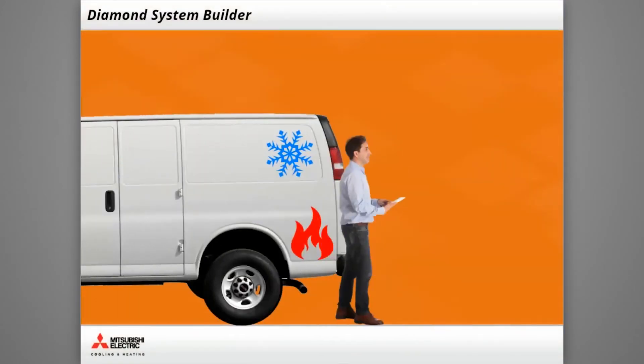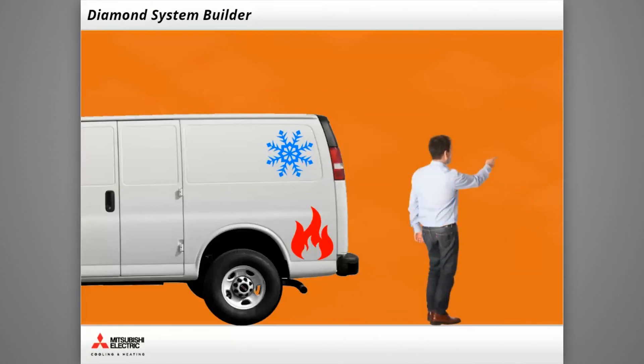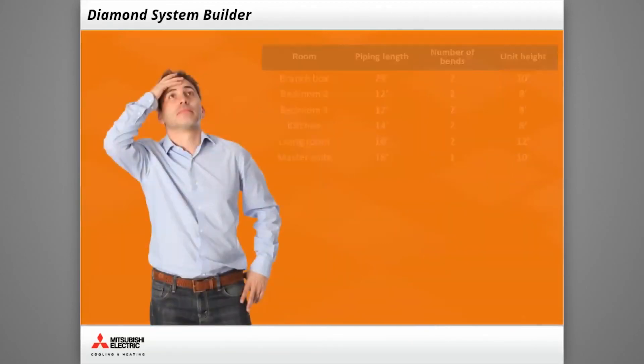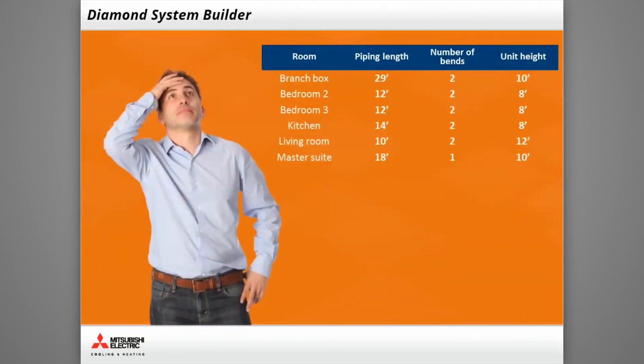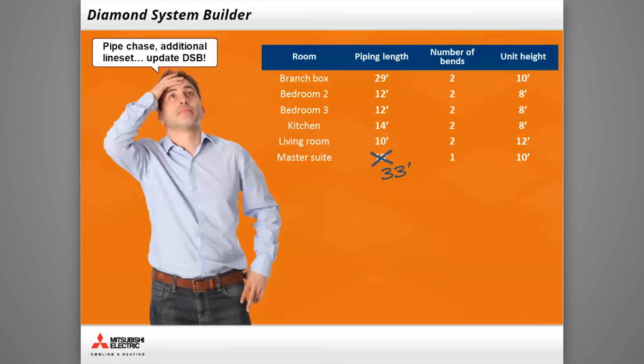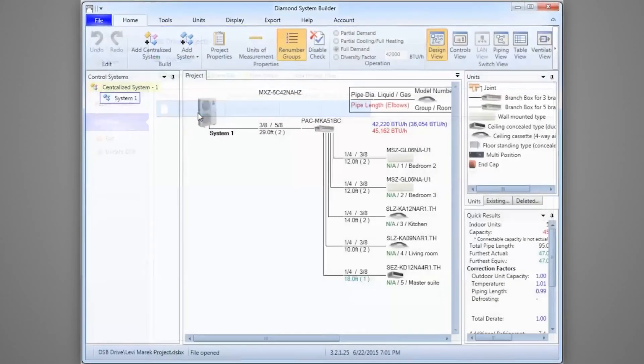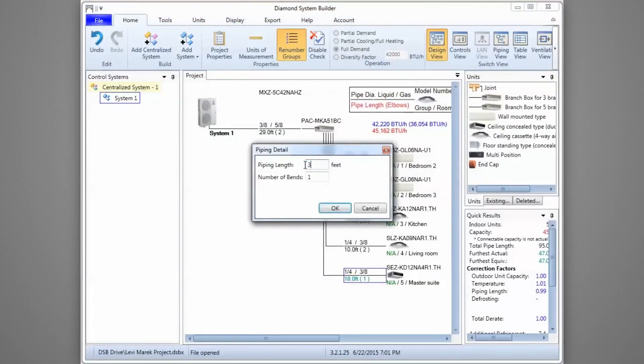Not all installations go according to plan. In some cases, changes to the design are necessary to get around unforeseen obstacles. In our scenario, we need to adjust our design to accommodate for a pipe chase — instead of 18 feet, we need to install 33 feet of line set. With any design change, return to DSB and update the project. Open the project, locate the unit line set needing to be changed, update the piping length, and click OK to confirm the change.